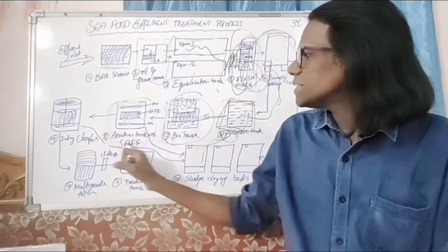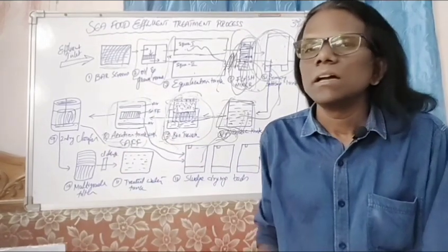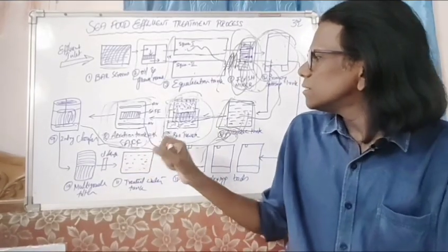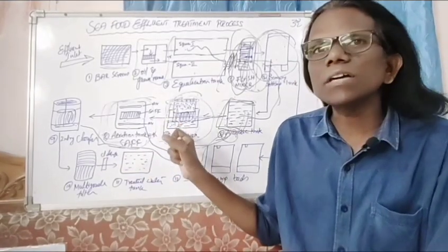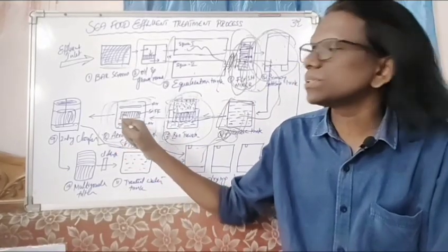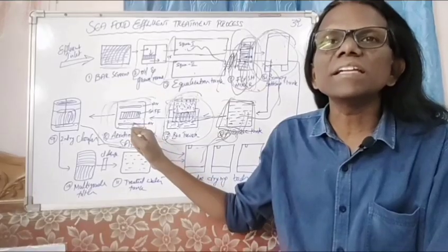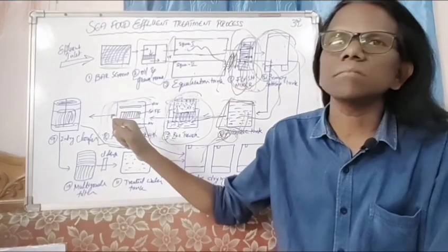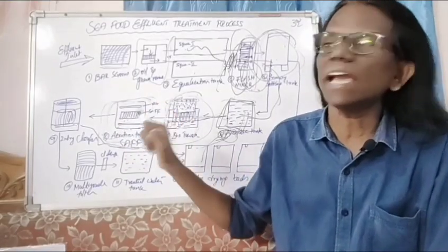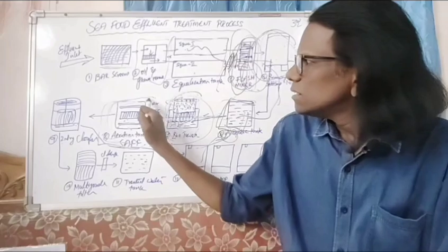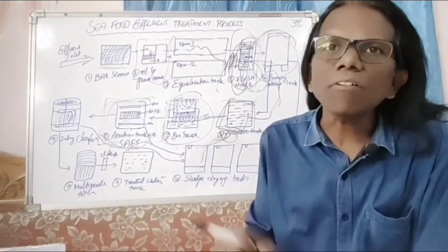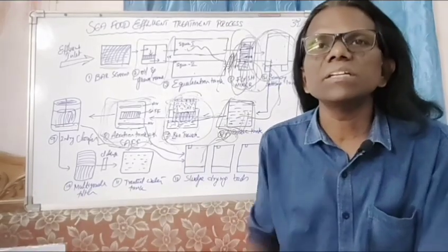Now the aeration tank. Here aerobic degradation will occur. The effluent water from the biotower goes to the aeration tank. The bottom of the aeration tank contains air diffusers, which will generate and maintain the oxygen levels in the entire system. We should always maintain oxygen levels of 2 mg per liter or above in the aeration tank as well as in the biotower. Most seafood industries or food processing industries have equipped an SAFF reactor mechanism in the aeration tank.